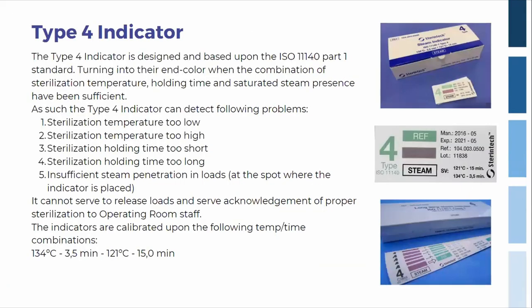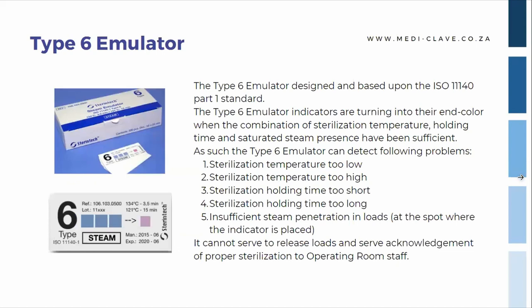So I'm just going to have a quick overview of all of those mentioned. Your type 4 indicator consists of a long and a short indicator. They test for sterilization temperature too low, sterilization temperature too high, holding time too short, holding time too long, insufficient steam penetration and load at the spot where the indicator is placed. It cannot serve to release loads and serves as acknowledgement of proper sterilization to operating rooms and staff. Your type 6 emulator tests the same as your type 4. It's not much different. It can also not serve to release loads and serves as acknowledgement of proper sterilization to operating rooms.